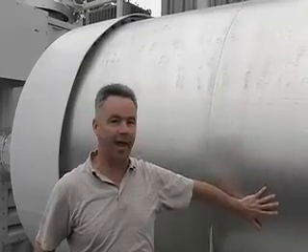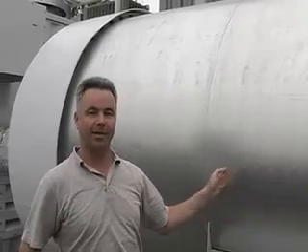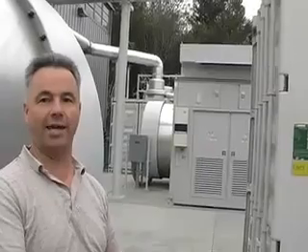This is called the stack — it's very warm. This is where the electrochemical reaction happens; it's about 1,200 degrees in there, and they have all the fuel cell parts stacked up so that the hydrogen reaction takes place. This part over here is called the mechanical balance of plant — it has all the mechanical parts: blowers, reverse osmosis, and the control system. The last part, back over here, is called the electrical balance of plant. That's the inverter, where the DC is converted to AC and dumped onto our power grid.